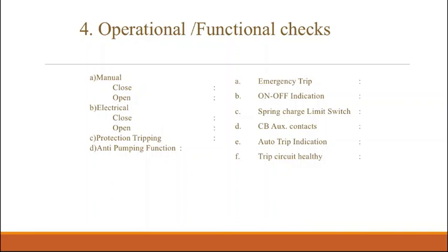If there is any protection fault, and the tripping is extended, the breaker has to trip. Anti-pumping function we have to check. If there is an emergency trip, we have to extend it and check whether the breaker is tripping or not. Those things we have to check. ON/OFF indication, spring charge limit switch status.